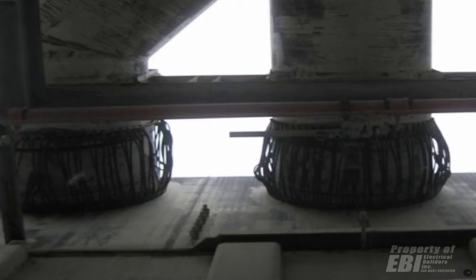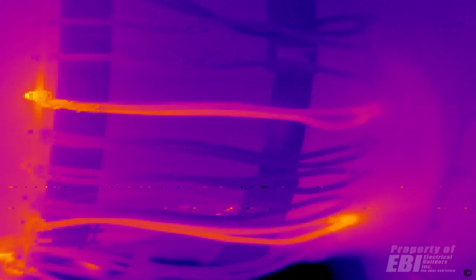And if you look at this with an IR scan, you'll notice that the cable that has the best connection also gets hot. It will eventually burn up, which then it carries all the current that it was carrying to the next best connection. That one will get hot and it will burn up. You have a cascading effect, then you start losing a majority of the cables, and it keeps getting quicker and quicker. And you can actually lose the entire grounding system on your bus once you lose enough of the cables.